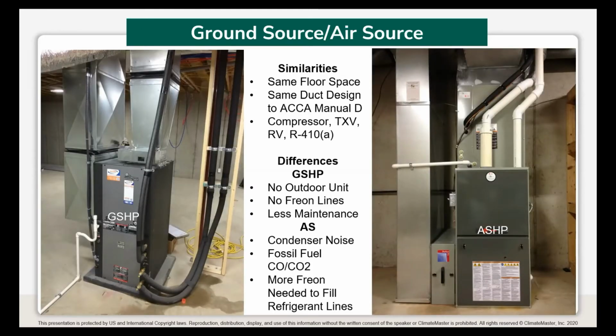So in a residence, what do the differences look like? On the left-hand picture, we have a ground source heat pump, right? On the right, we are looking at an air source heat pump, with either an electric air handler or a gas furnace. And we have copper tubing connecting an indoor evaporator coil, and you see that in your own basements or homes. That connects to a condensing section sitting out in your yard. And then we have supply and return ductwork that is delivering conditioned air to the living space.